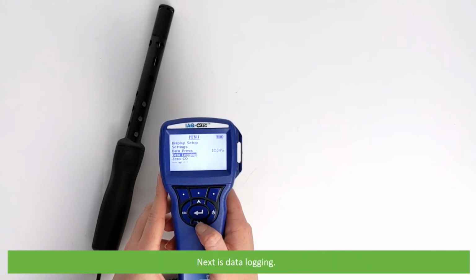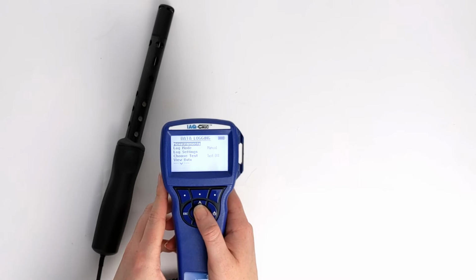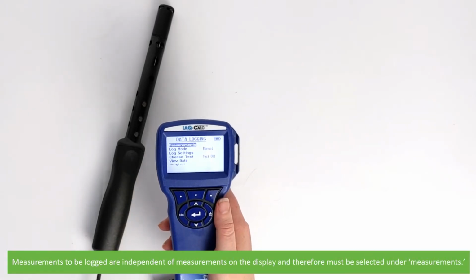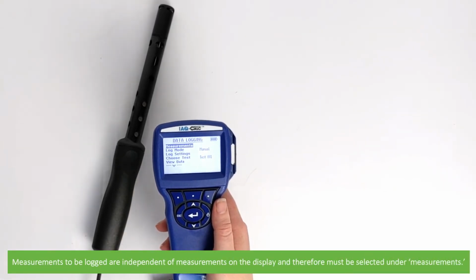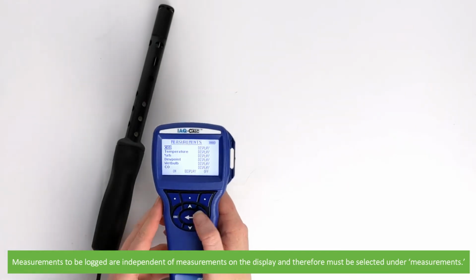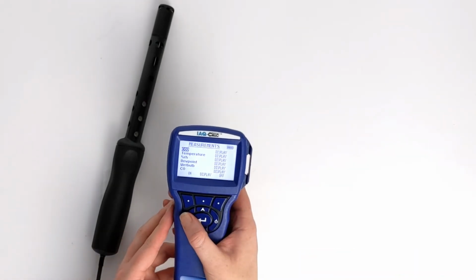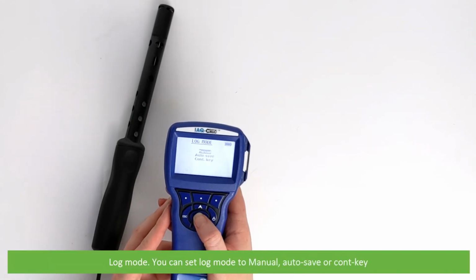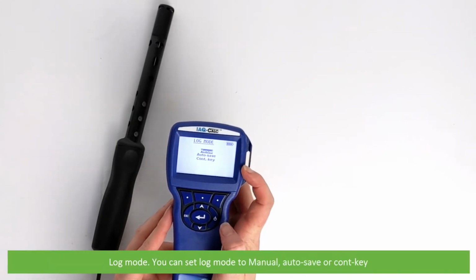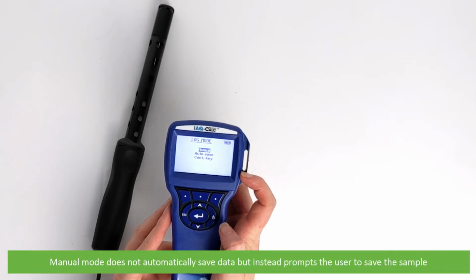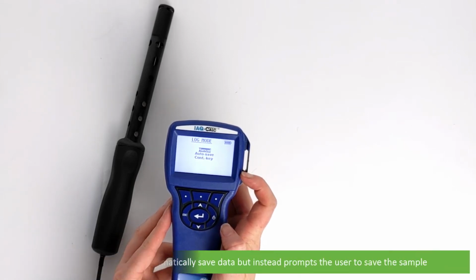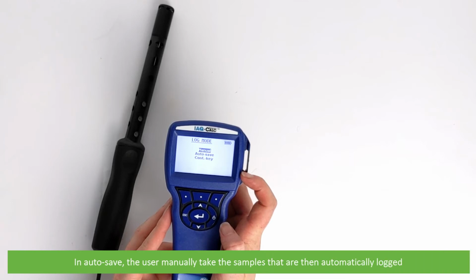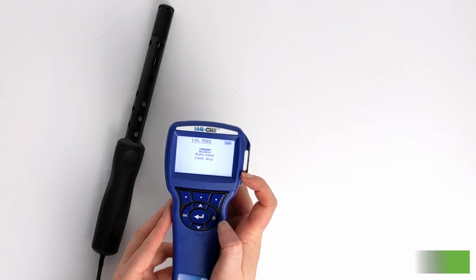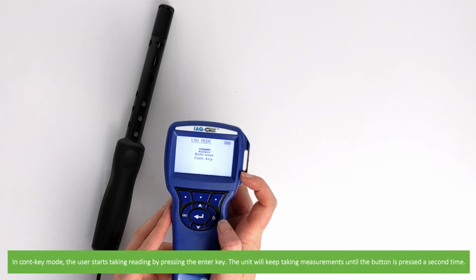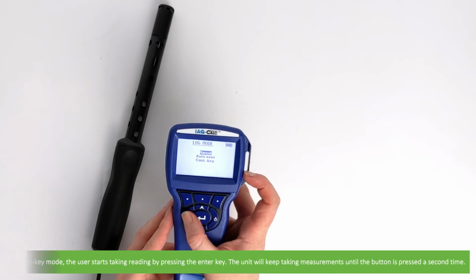Next is data logging. Measurements to be logged are independent of the measurements on the display and therefore need to be selected under measurements. Log mode. You can set log mode to manual, autosave, or cont key. Manual mode does not automatically save data, but instead prompts the user to save a sample. In autosave, the user manually takes the samples that are then automatically logged. In cont key mode, the user starts taking a reading by pressing the enter key. The unit will then keep taking measurements until the button is pressed a second time.